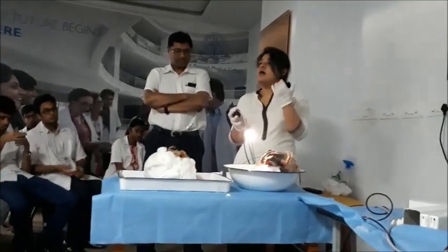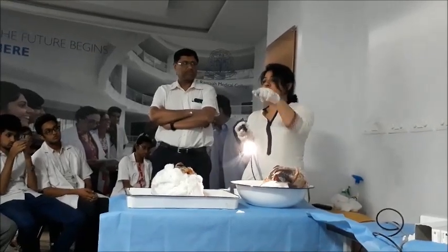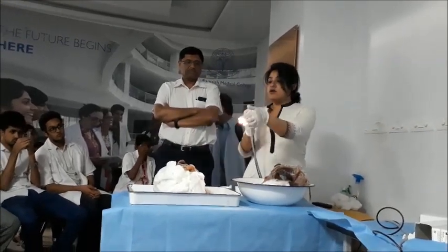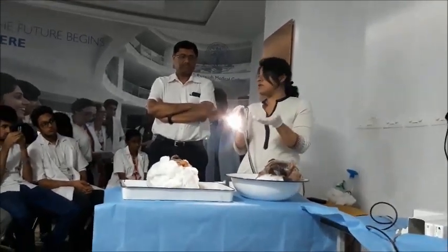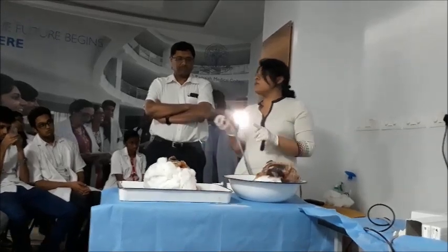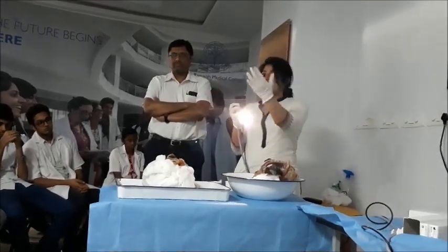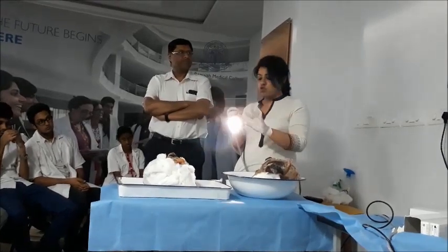So if you have to look at the larynx, if I pass a straight endoscope into the throat, the lens will look downwards, so it will be able to pick up something that is down there. Now for an ear endoscopy, we will be using a 0 degree endoscope, which looks directly in front of the endoscope. It's 0 to the horizontal.